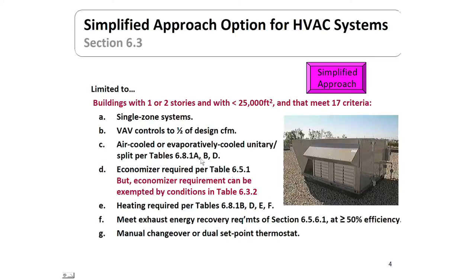Let me first cover the simplified approach because that would get you through to compliance the quickest. It does require you to have a fairly simple building — one to two stories and less than 25,000 square feet. It also has to meet all 17 of the listed requirements. It has to have single zone systems: it can have multiple zones in the building, but each system has to serve just one single zone.